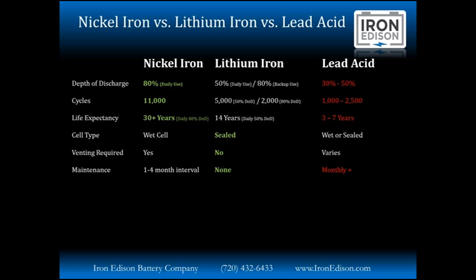Depending on how aggressively you're charging and using the battery, you'll have to top off the electrolyte with only distilled water every 1 to 4 months. And that's it for maintenance. With nickel iron batteries, you do not need to do equalization charges that you do with lead acid batteries. Also with nickel iron, you do not need to check the specific gravity. All you do is top them off with distilled water.